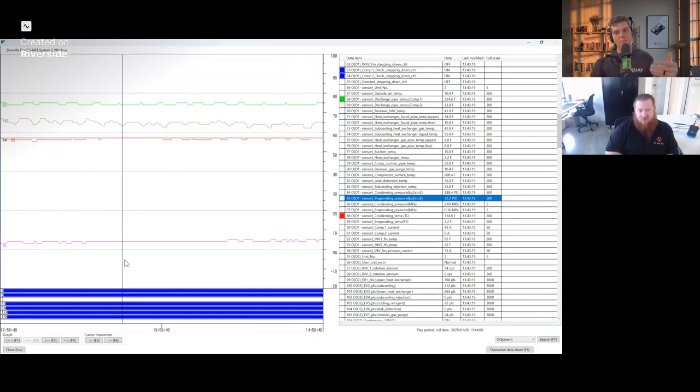That's actually subcooling because you're actually building it up. But again, the unit's not restricting anything. Low pulses in heating inside, high pulses outside is the same equivalent in cooling mode where pulses are high inside and pulses are low outside, right? You ain't got no flow. You ain't got no gas, man.